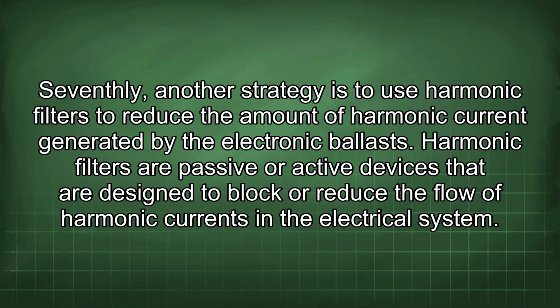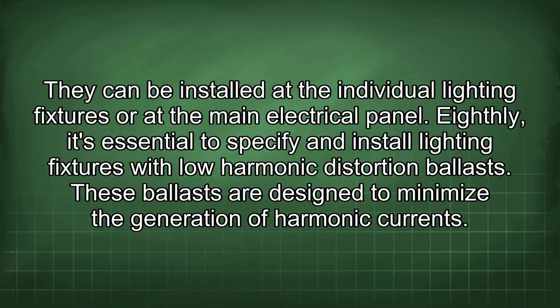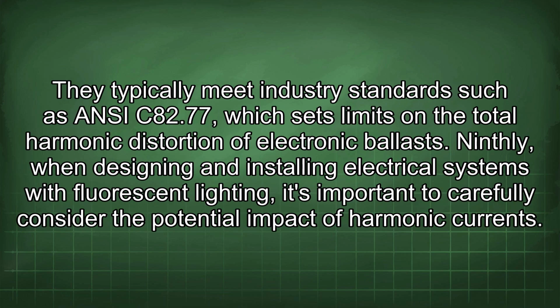Harmonic filters are passive or active devices that are designed to block or reduce the flow of harmonic currents in the electrical system. They can be installed at the individual lighting fixtures or at the main electrical panel. Eighthly, it's essential to specify and install lighting fixtures with low harmonic distortion ballasts. These ballasts are designed to minimize the generation of harmonic currents.